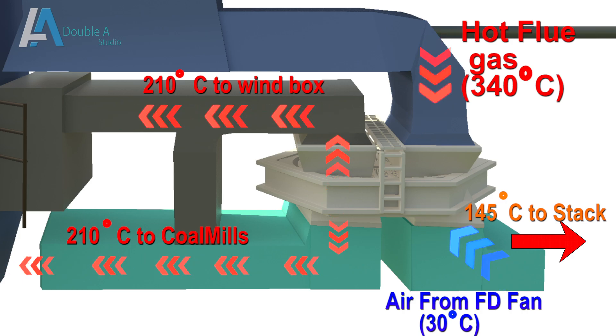Because flue gas contains SOX and NOX gases, they may combine and form acid with moisture. So to prevent corrosion of metal parts, optimum temperature at exhaust is maintained.